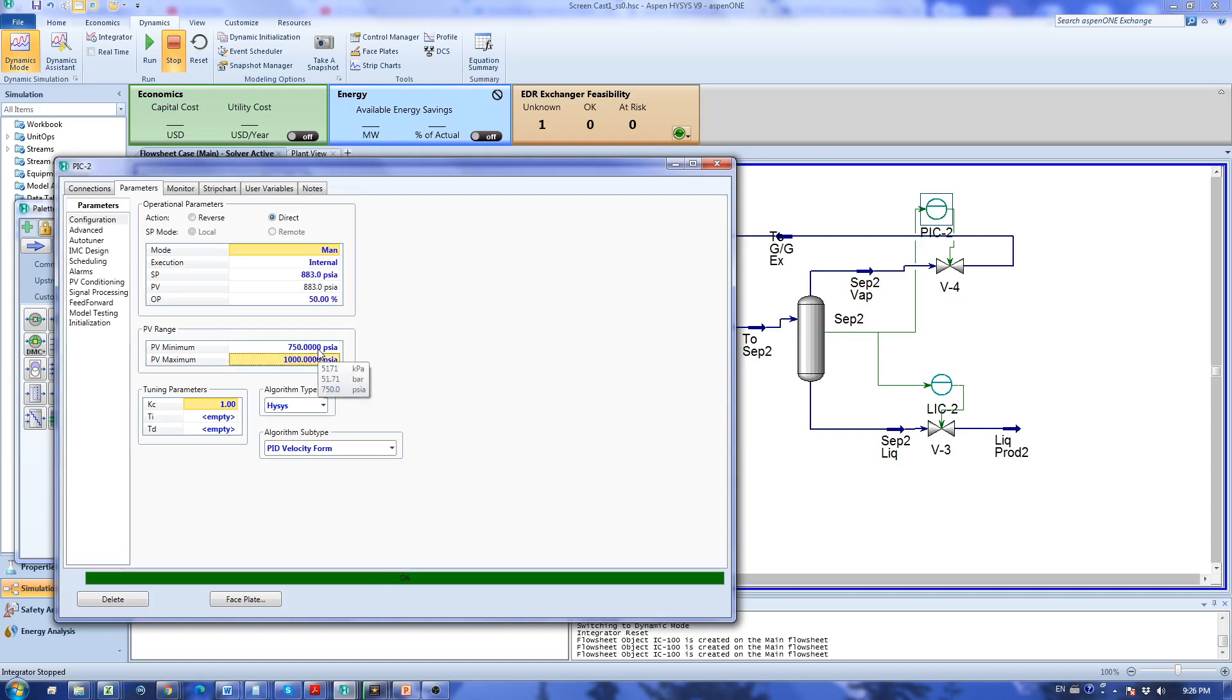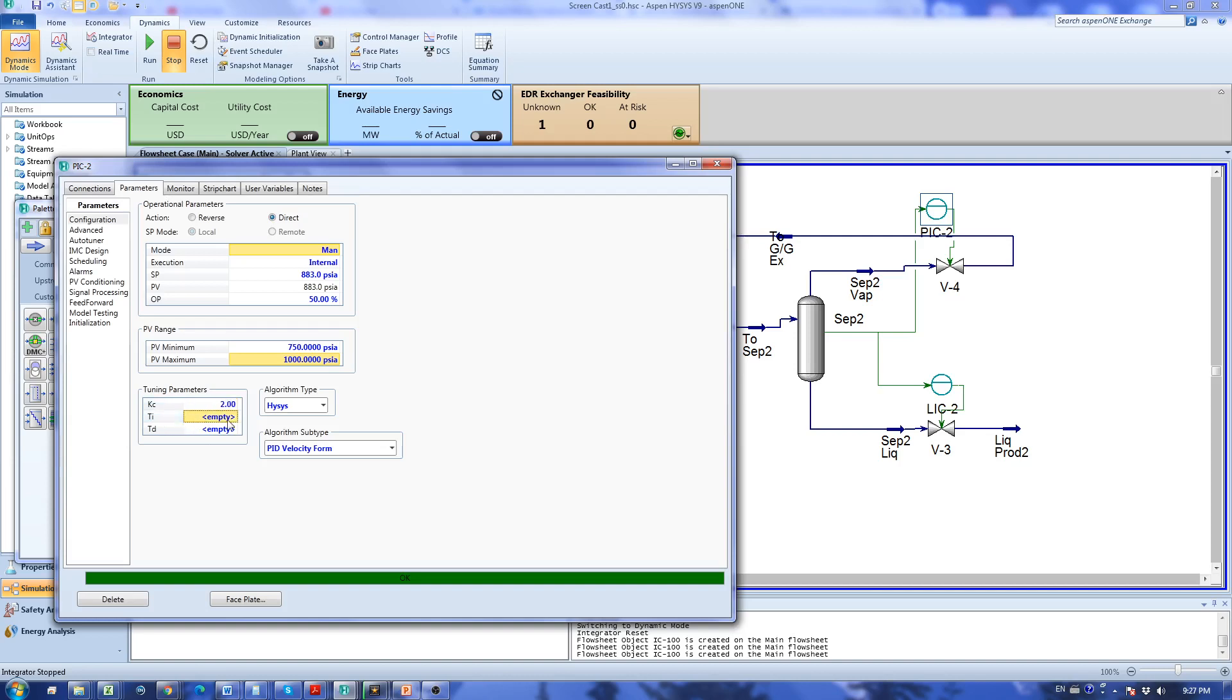For the tuning parameters for the pressure I like to keep the pressure at a constant value because I don't want to cause upsets. I can't tolerate up and downs in the pressure so I specify a proportional constant kc of 2 and I'm going to specify also an integral variable.